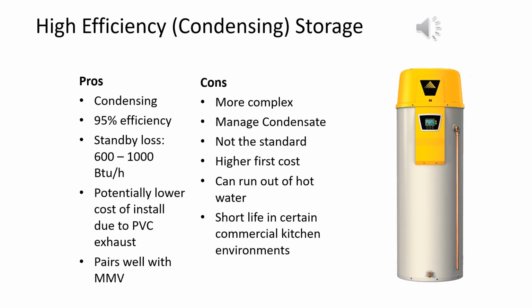Condensing water heaters are more efficient than standard storage water heaters. They work by running extra lengths of exhaust through the water tank. This cools the exhaust and allows the water in the combustion exhaust to condense, which provides more heat to the water in the tank. The pros are that these heaters boast a 95% efficiency, they can have a much smaller standby loss because they're usually insulated, there's potentially a lower cost of install because sometimes these heaters can be installed with a PVC exhaust instead of standard ducting, and these pair very well with master mixing valves and demand recirculation controllers because their condensing function requires tank stratification to work.